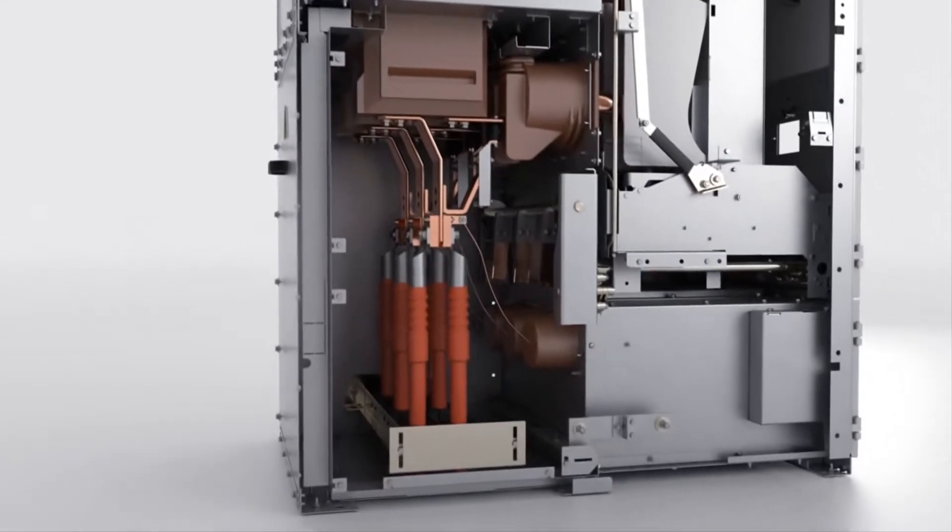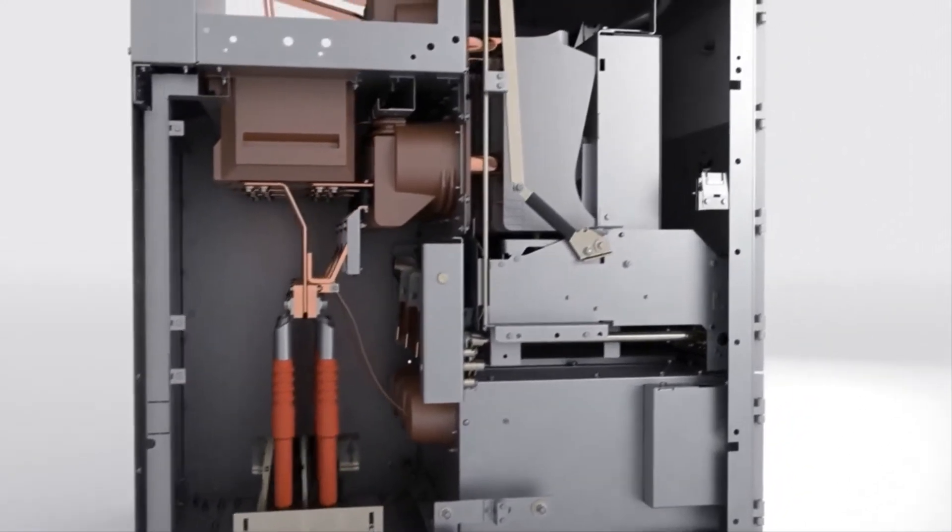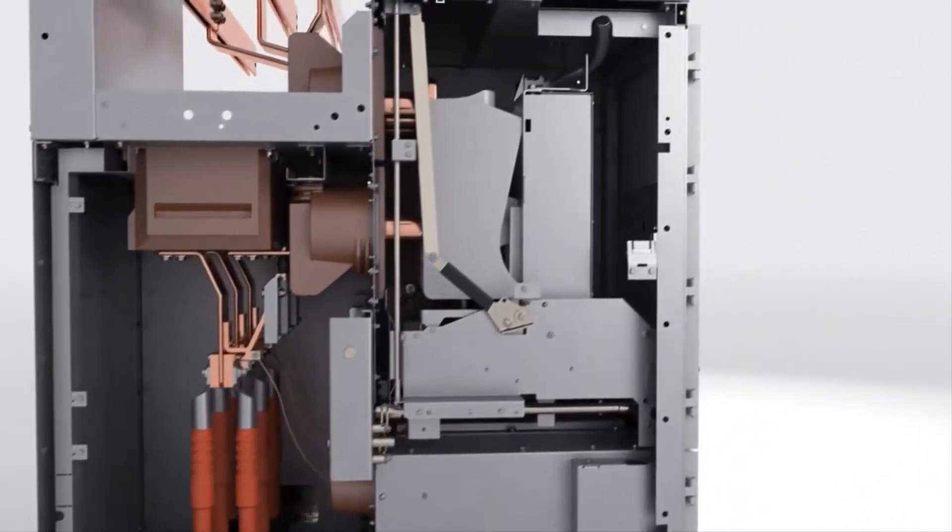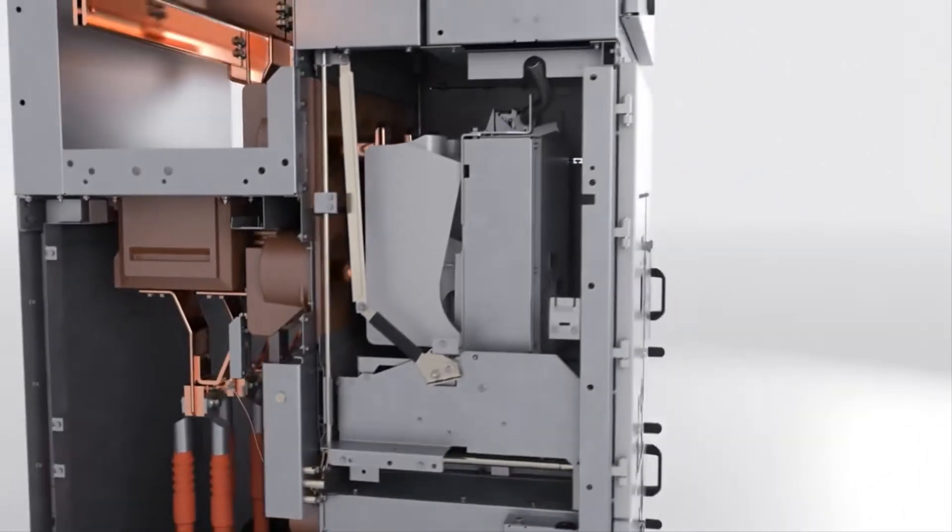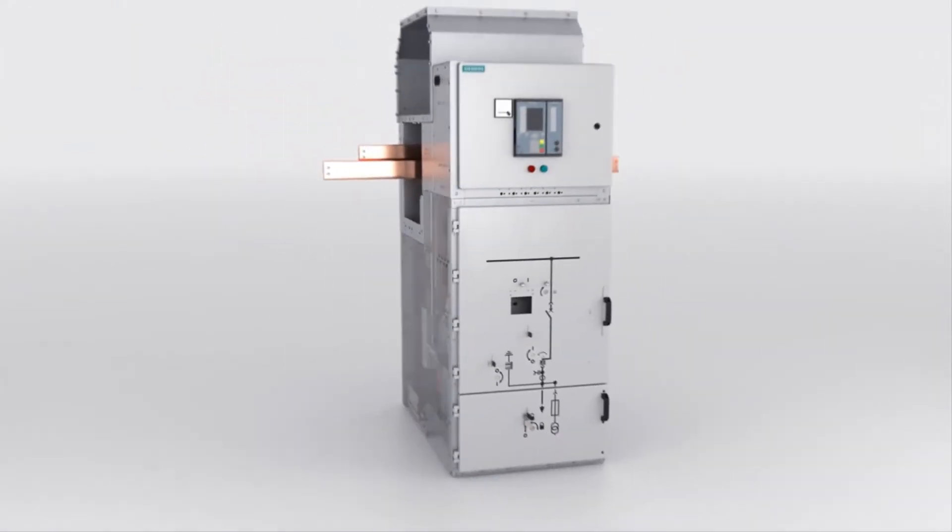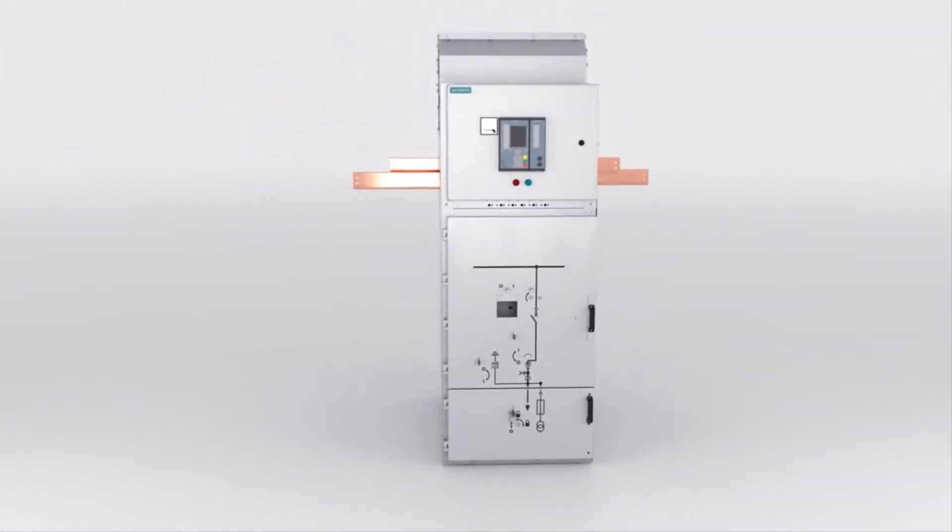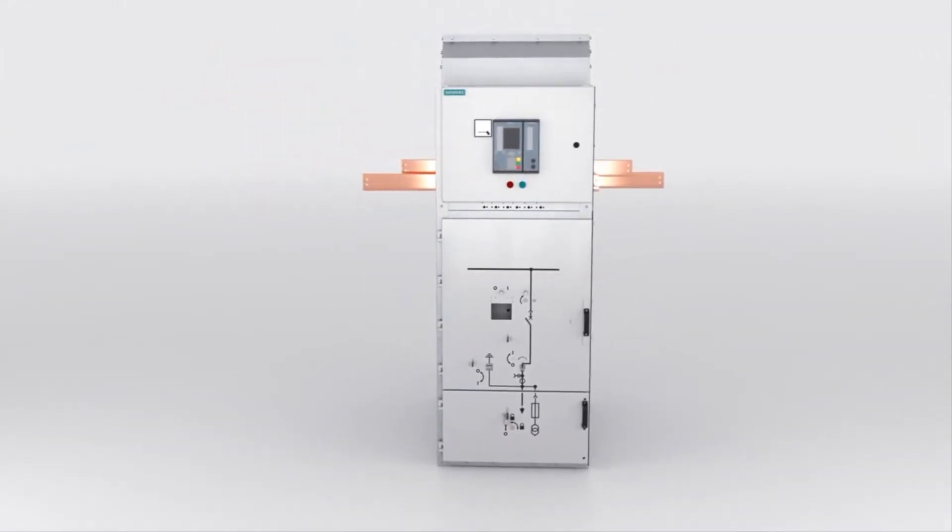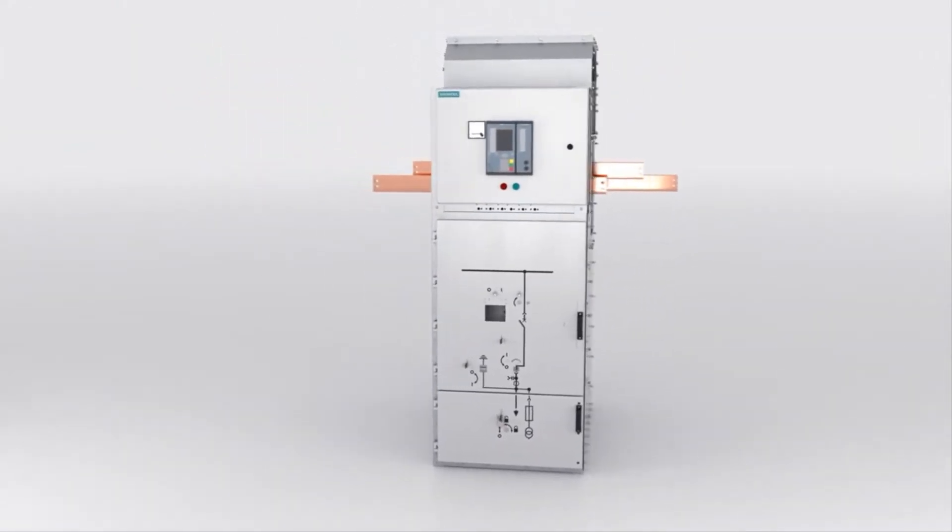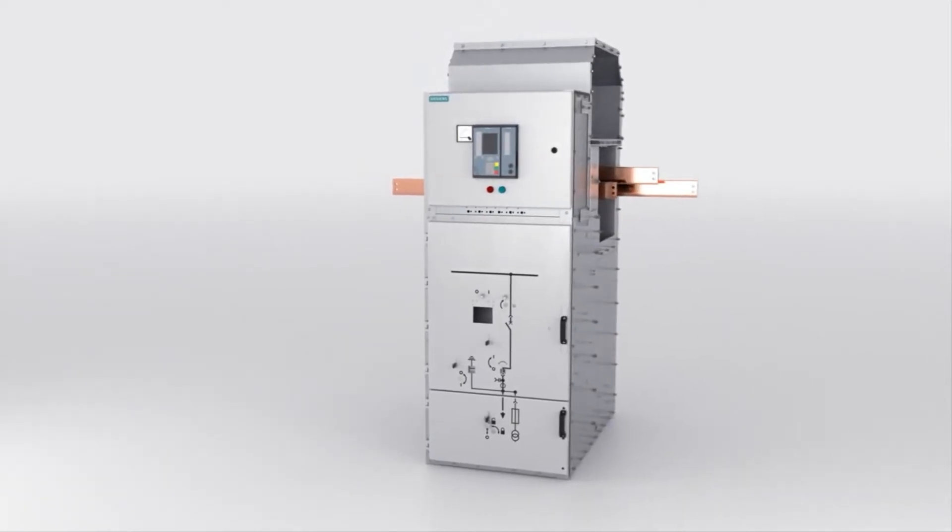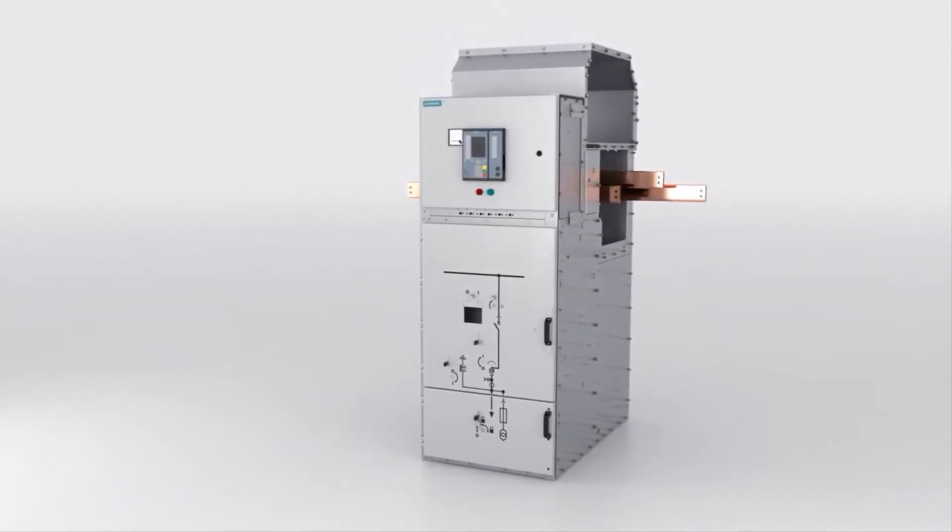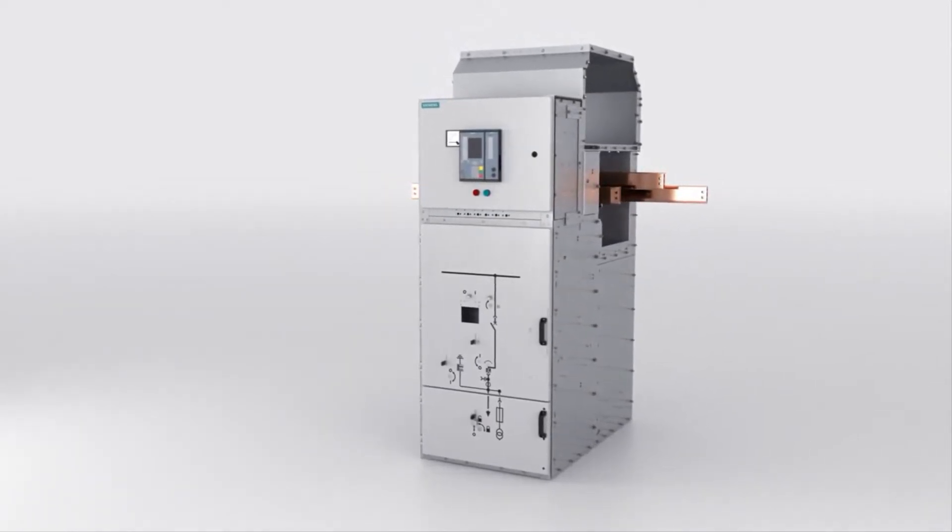Switching operations are possible only when the high-voltage door is closed. Even switching operations to eliminate faults, such as a cable fault in a specific feeder, can be conducted without isolating the bus bar and thus without interrupting the rest of the distribution system.